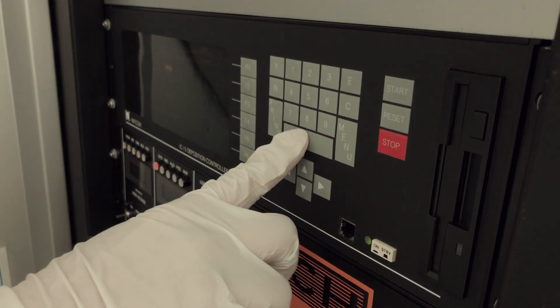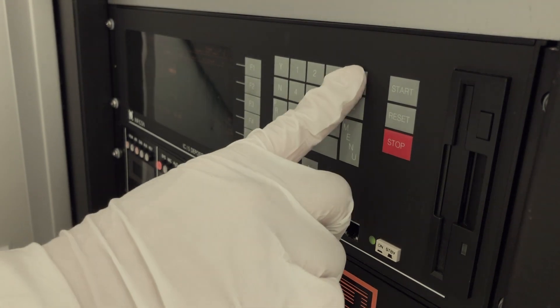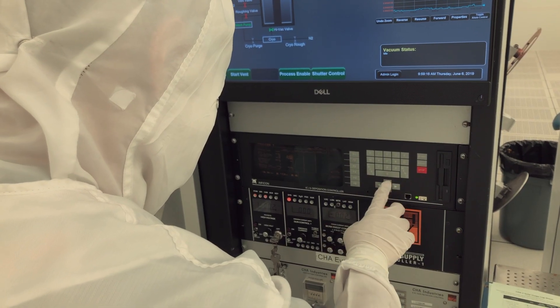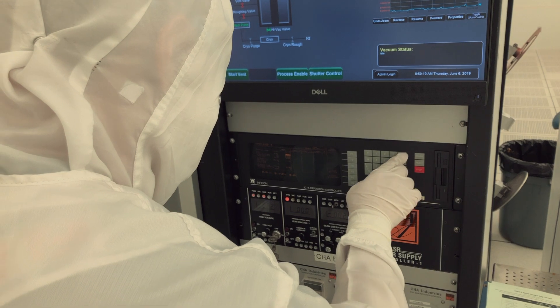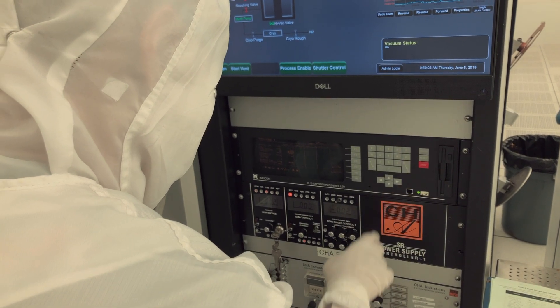You should only change the deposition rate, final thickness, and thickness limit. Typical deposition rates range from 1 to 3 angstroms per second. Ensure that the values set for the final thickness and thickness limit are set to the same value.